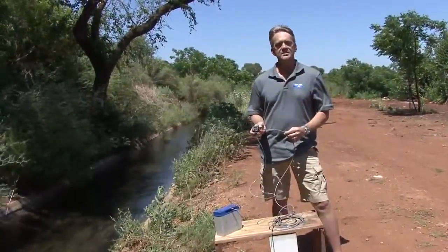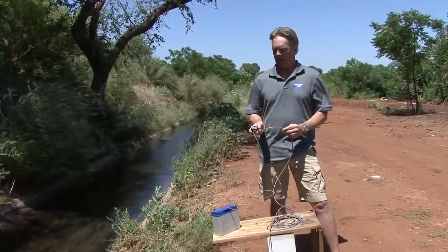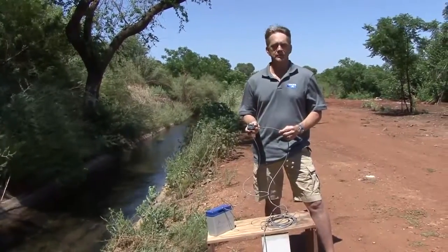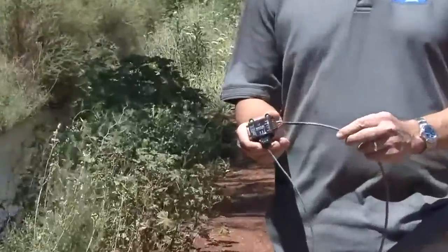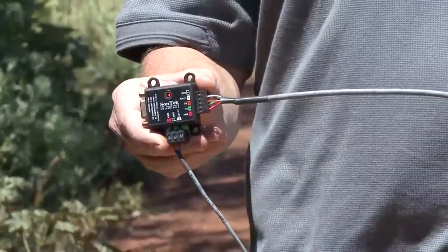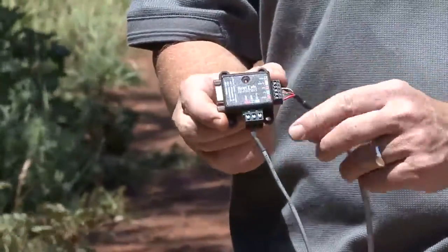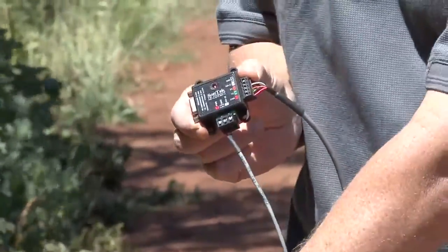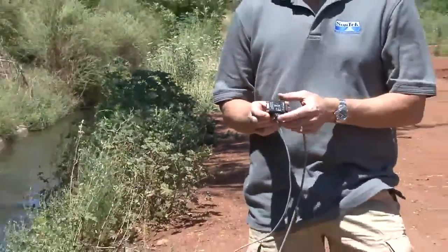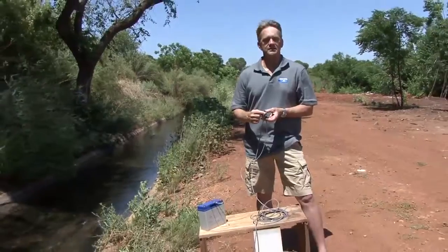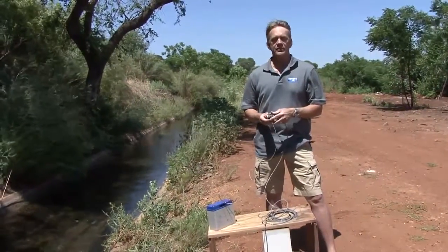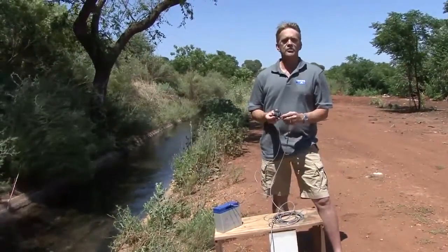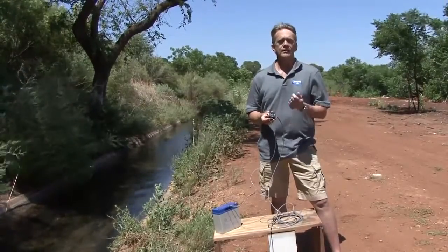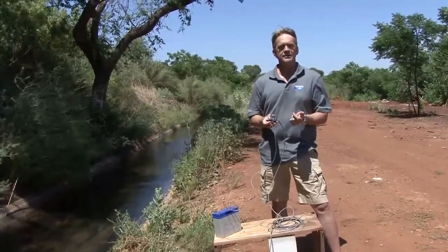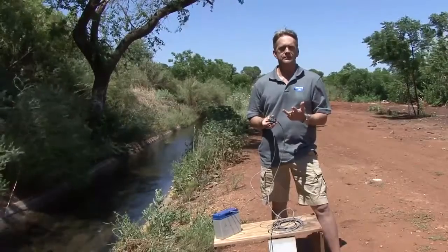Okay, what I have here is the SonTek-IQ Power and Communications Interface module. Using this module, I connect the IQ using this cable. I apply power. You can see I have a small 12-volt power supply there. And this is where I have my communications. I have a variety of communication options, first being SDI-12, 4-to-20, Modbus, and of course RS-232.